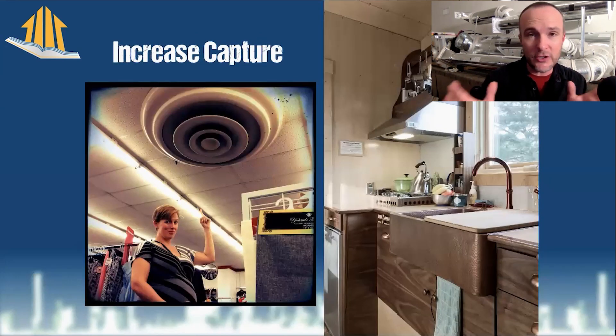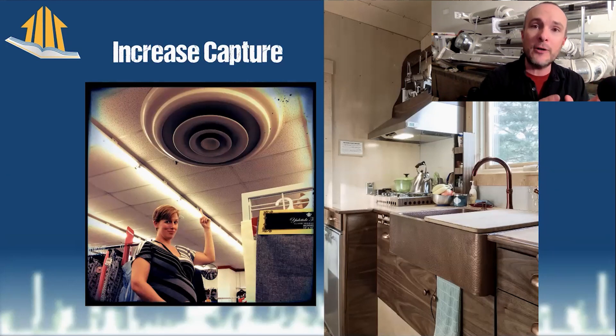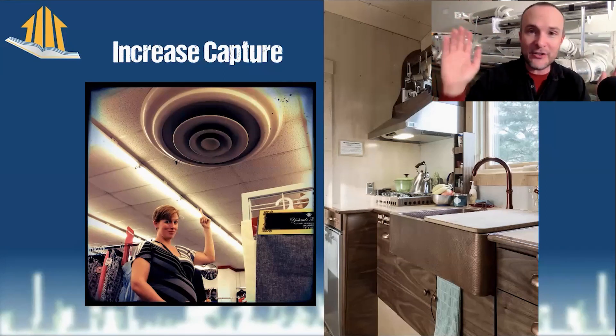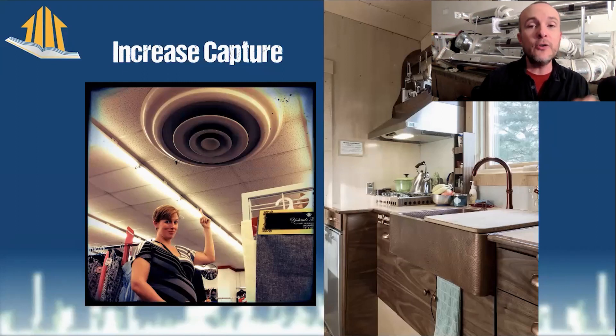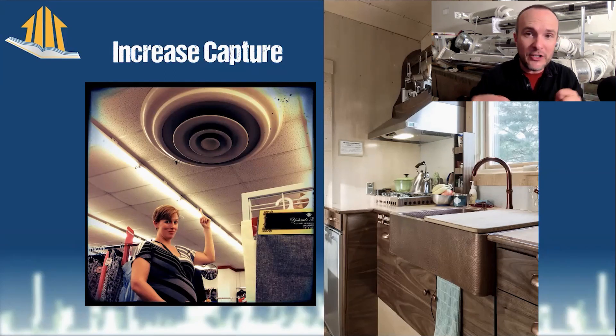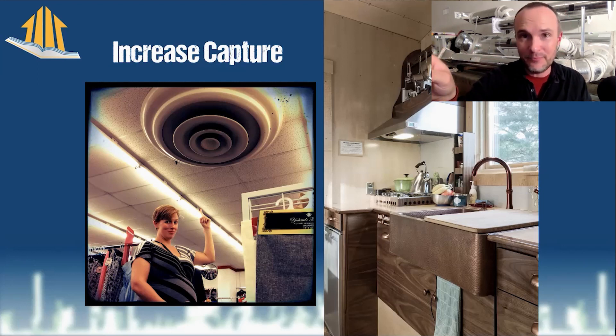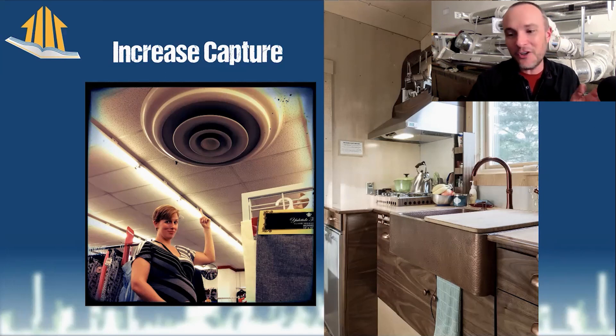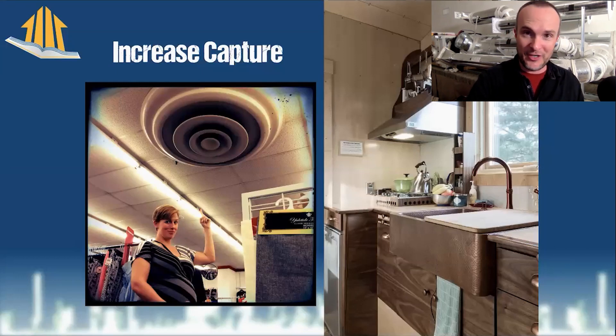To increase capture, you can use two things broadly: fan power — you could have a 2,000 CFM kitchen exhaust if you really want to — or geometry, where you nestle a lower-power fan into a corner so it only draws air from two places, encouraging air from the cooktop to go out. If you put the cooktop on an island, you have to use fan power because you've lost the geometry advantage. Generally, using both is a good idea.